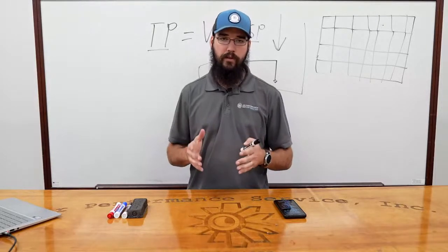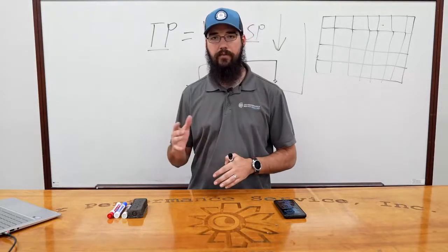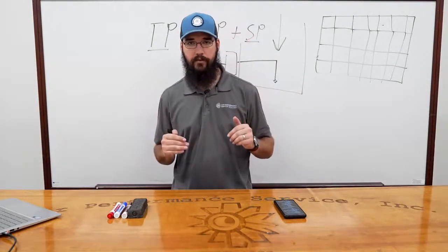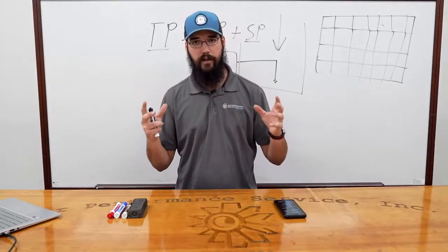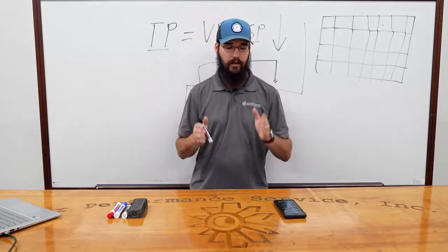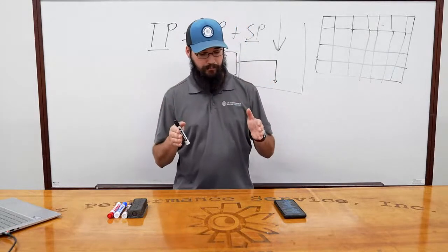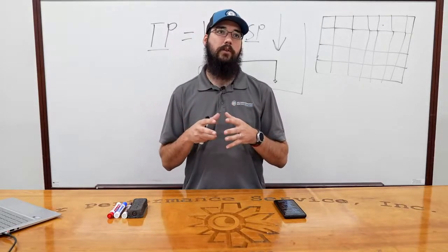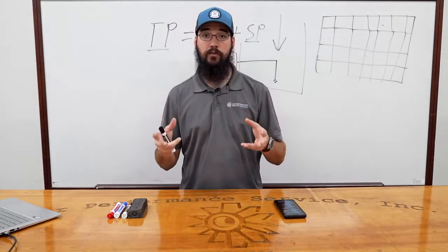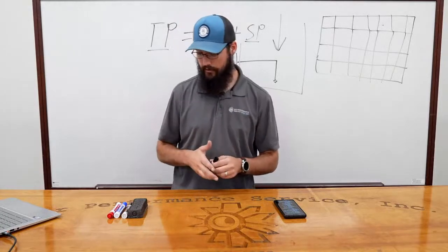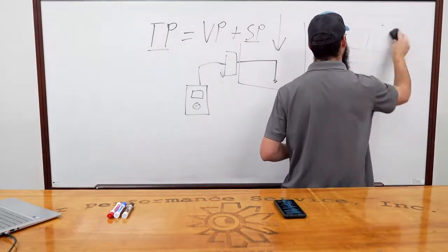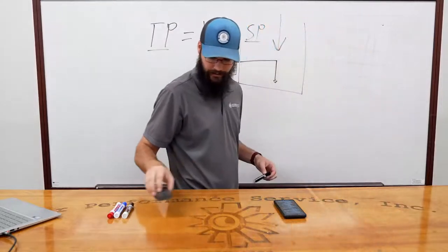So if you really need to know what your CFM is, and not just a general idea from external static that gives me some direction to go off of, no, I need to actually calculate my CFM, but I don't have an external static option, that's not on the table. That's okay. There are a couple of quick things you can do, but they involve the heating side. Now in the wintertime, this is no big deal, right? We want heat anyway.